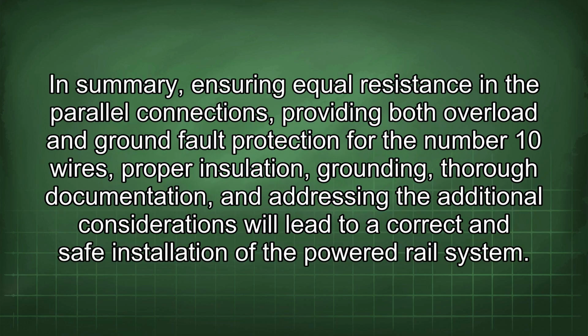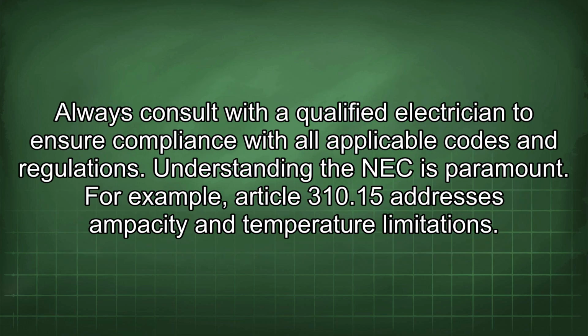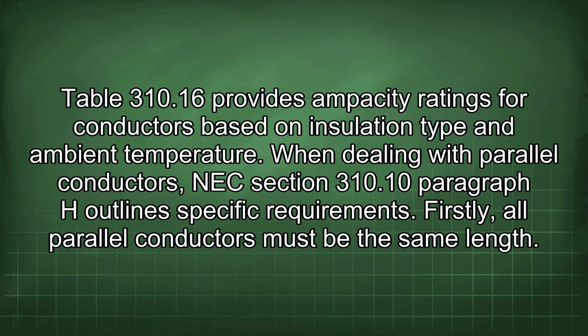In summary, ensuring equal resistance in the parallel connections, providing both overload and ground fault protection for the number 10 wires, proper insulation, grounding, thorough documentation, and addressing the additional considerations will lead to a correct and safe installation of the powered rail system. Always consult with a qualified electrician to ensure compliance with all applicable codes and regulations. Understanding the NEC is paramount. For example, Article 310.15 addresses ampacity and temperature limitations. Table 310.16 provides ampacity ratings for conductors based on insulation type and ambient temperature.